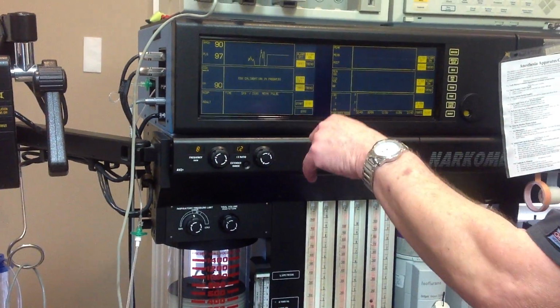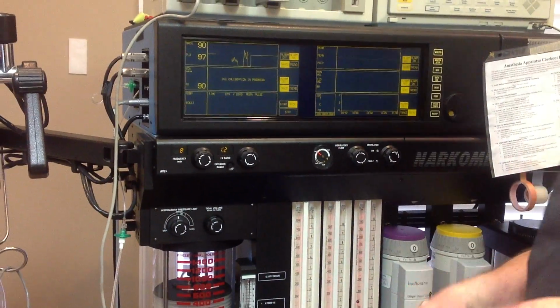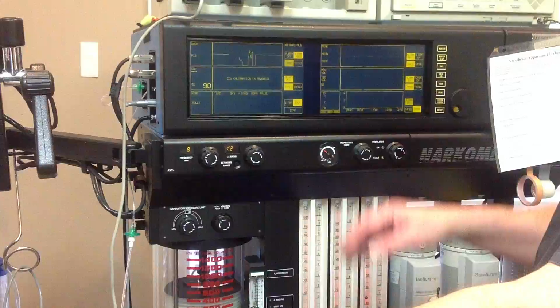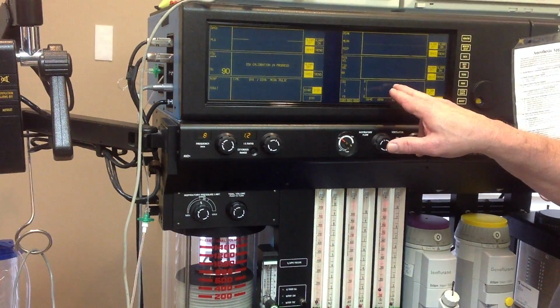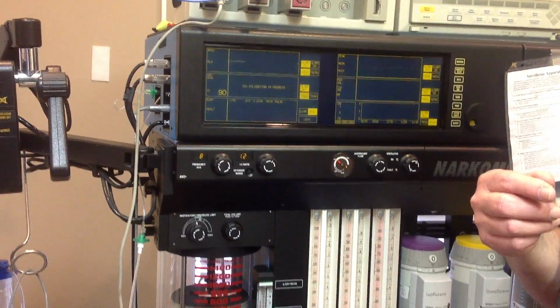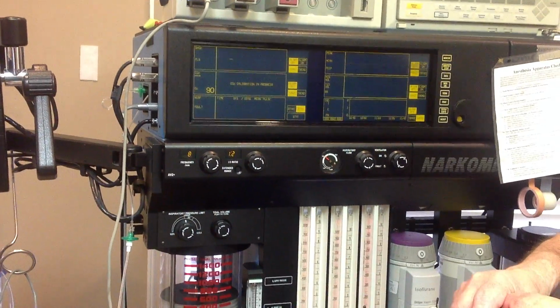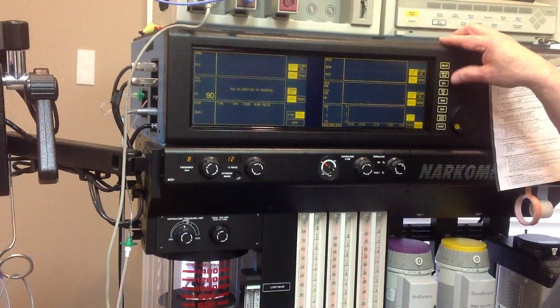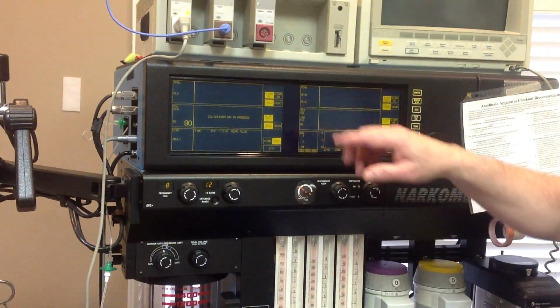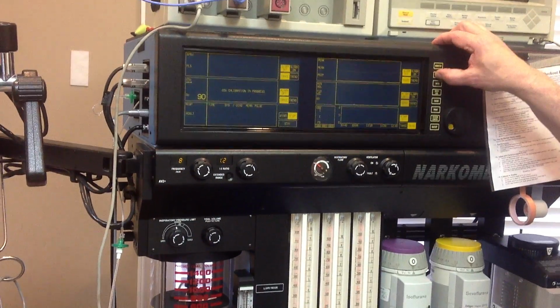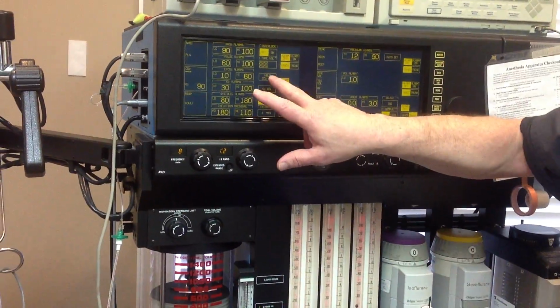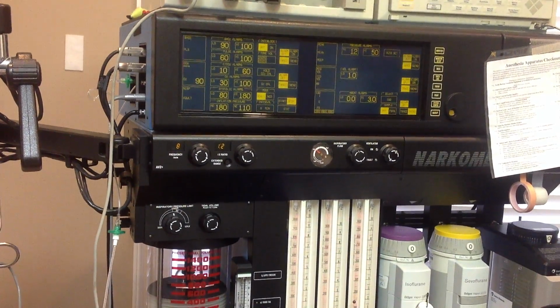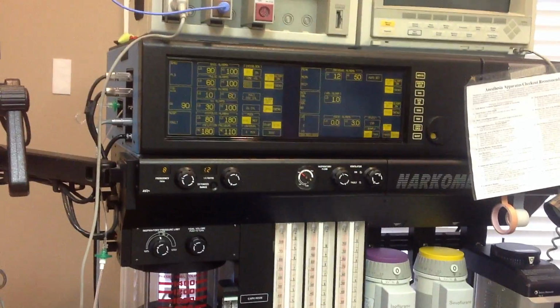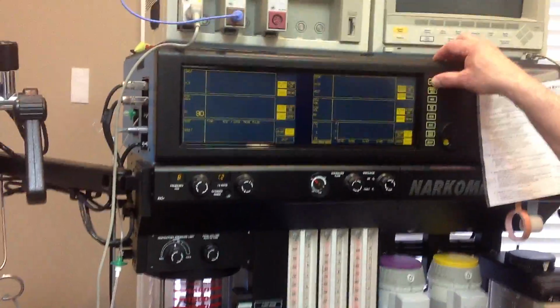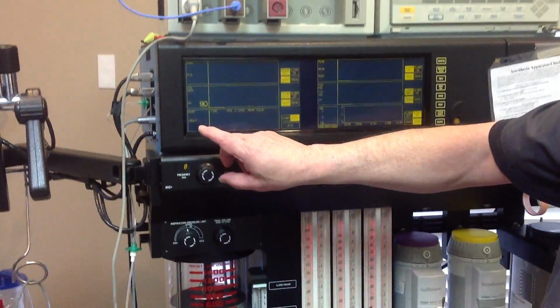Then my CO2 waveform. Now you see it says CO2 calibration in progress. Now we calibrate the FiO2 monitor, but everything else is self-calibration. The CO2 calibration, the agent analyzer over here will recalibrate every 15 minutes. Okay, and you'll see this CO2 calibration in progress. A while ago, when Tiffany was trying to intubate this patient, we were in CO2 calibration. So if we were ever in that situation, there's a button over here that says hold CO2 cal. So if you're getting ready to intubate and it's in calibration mode, you can hit that so that your CO2 monitor will work properly. All right, and this is my FiO2 monitor measured here.